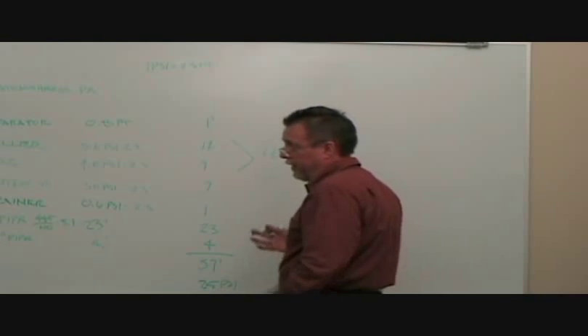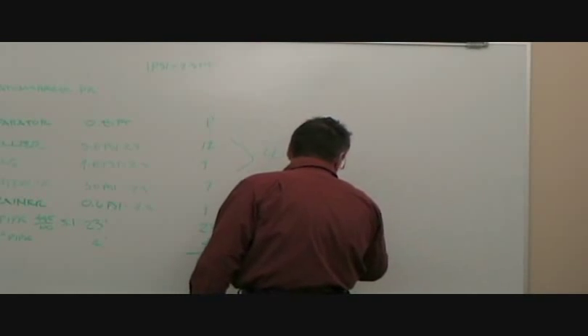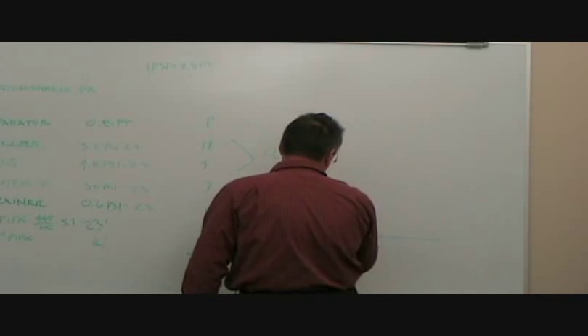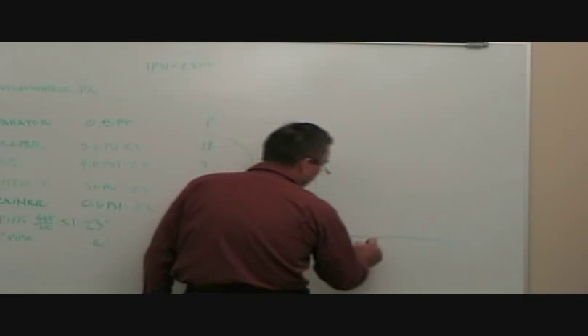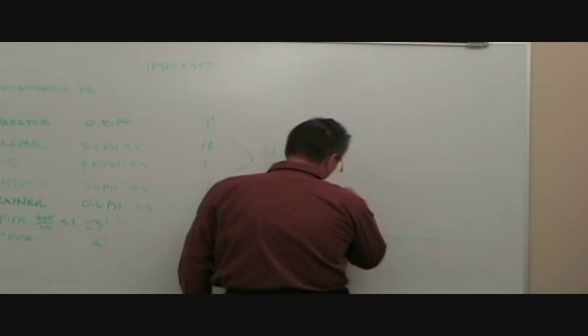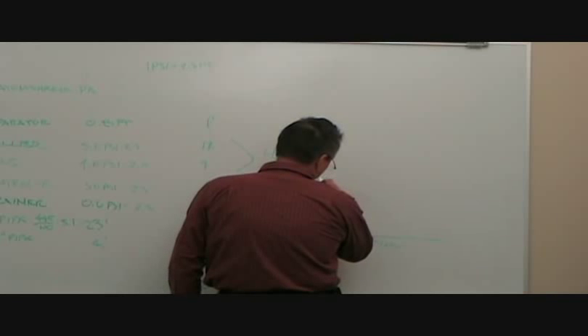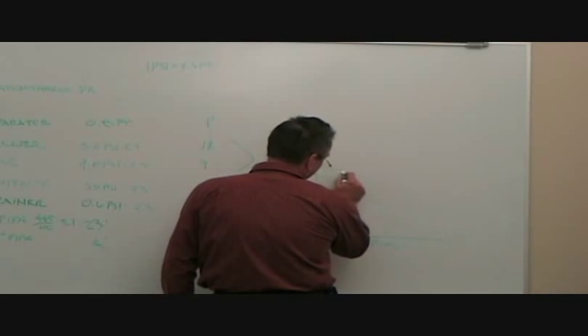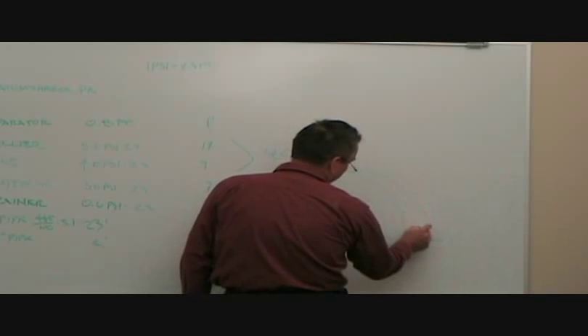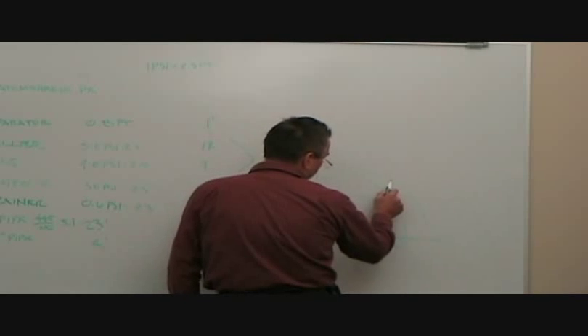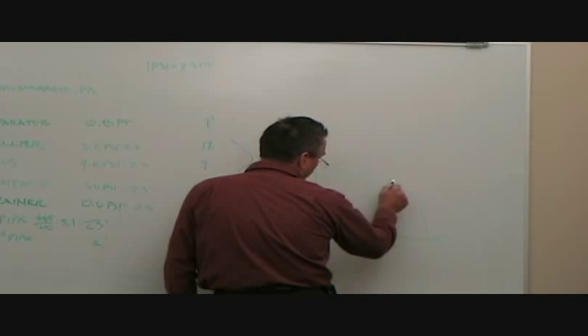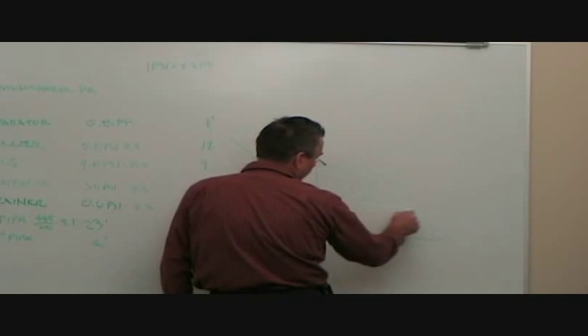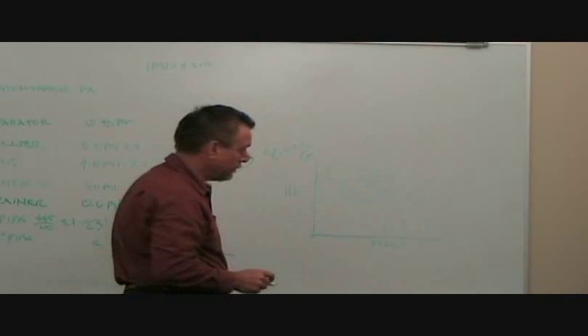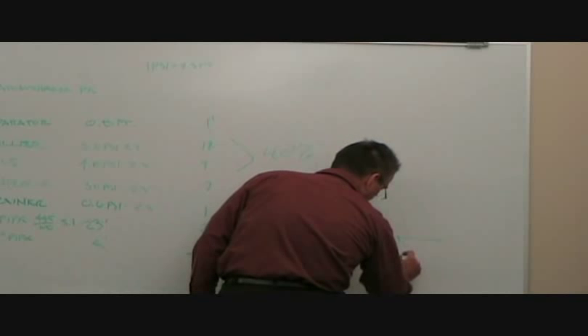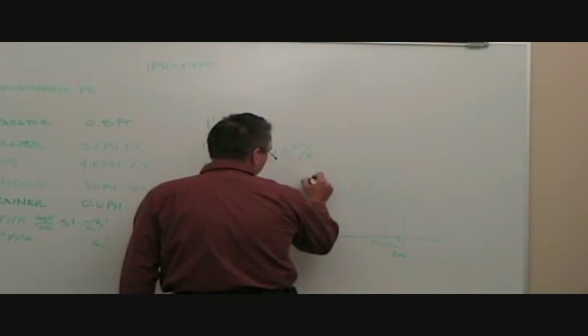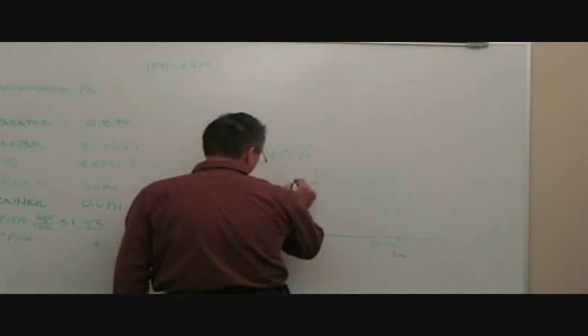I don't have any pump curves because I don't have access to them. But a pump curve looks like this: we've got head and flow, and you've got impellers inside each pump that operate something like this. Then I'll have little circles in here that show me efficiency. So right here is 200 gallons a minute, and right here is, let's say, just 60 feet of head.